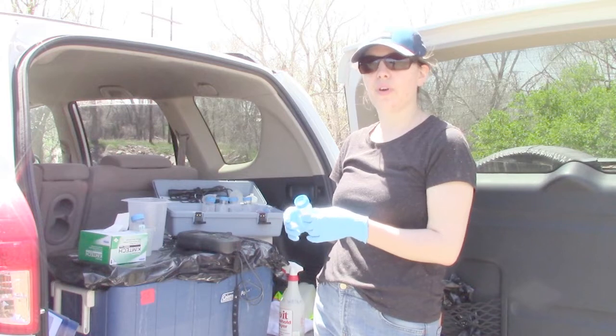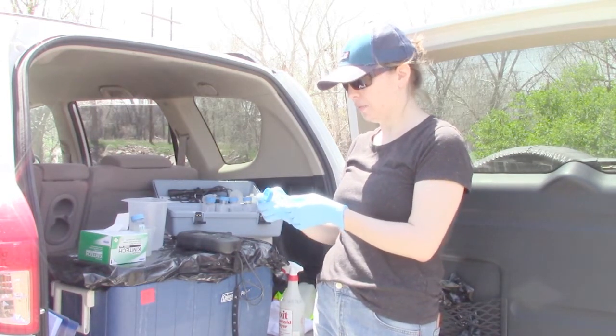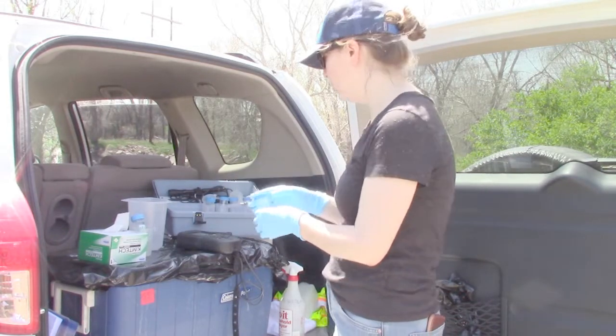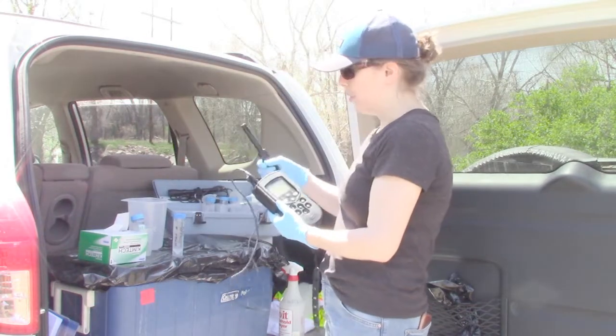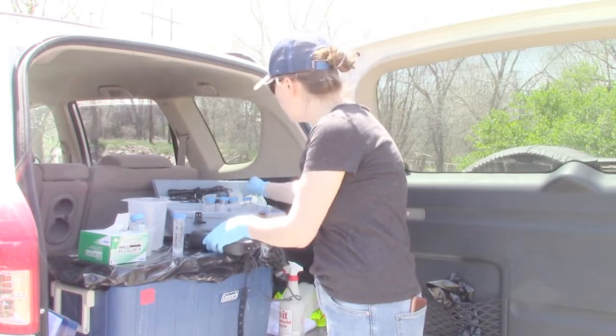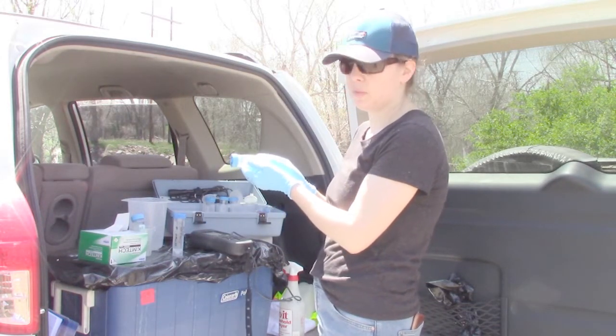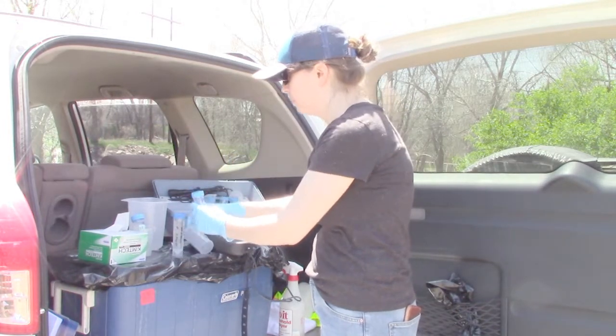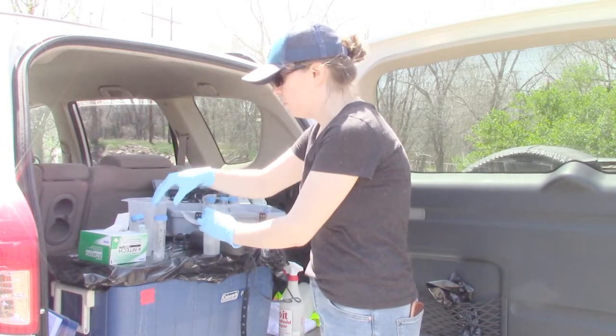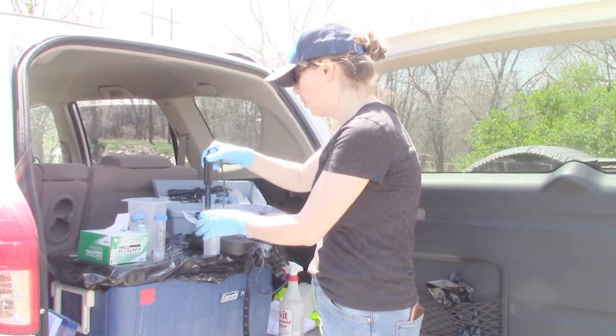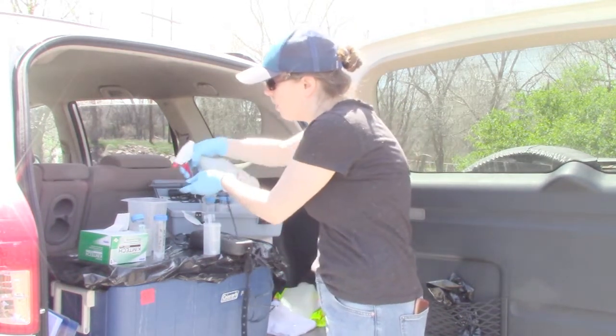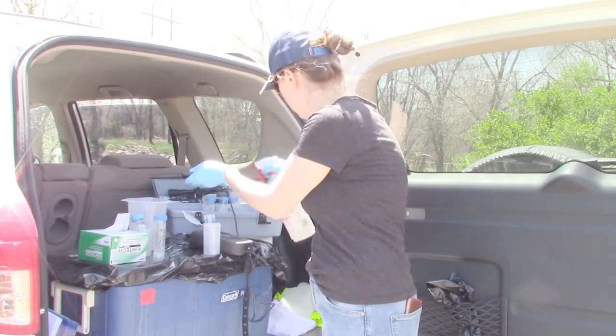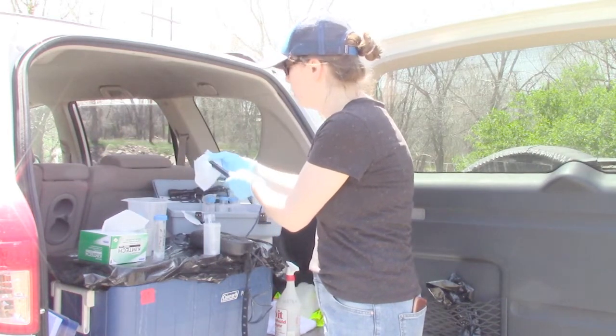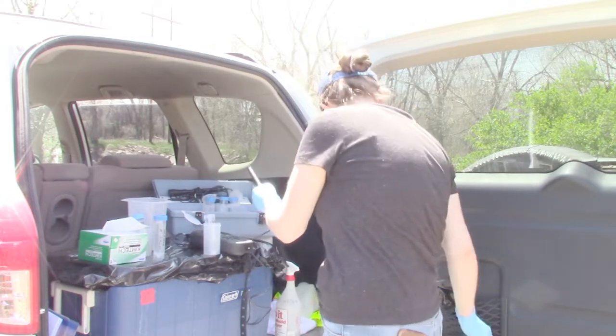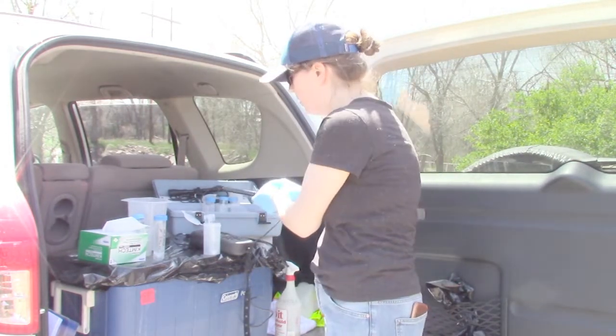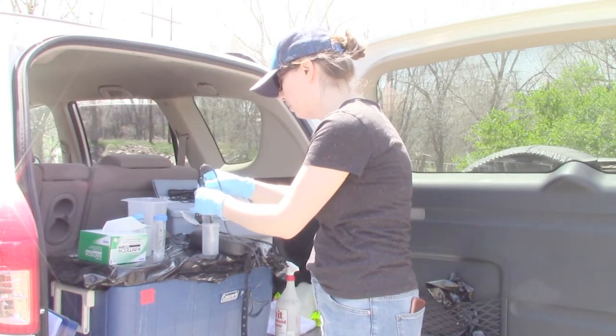The last measurement I'm going to show you today is the conductivity measurement. Again, we're looking at a sample from PC320. It's not filtered. So you would connect the conductivity probe onto the multimeter and turn it on. First we're going to calibrate it using the 1413 microsiemens per centimeter calibrant solution. Just as a warning, this morning the conductivity probe did not work. Oh sorry, first we would rinse it like always. Make sure that I'm following the protocols here. So the probe didn't work this morning, so we're going to try it again. It did calibrate, but in the end it didn't give us any reading when we measured the sample. So let's see what it does now.